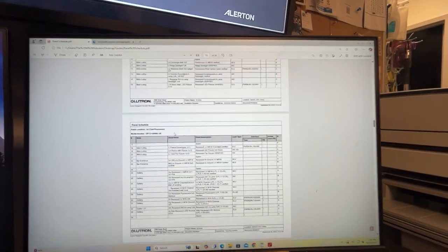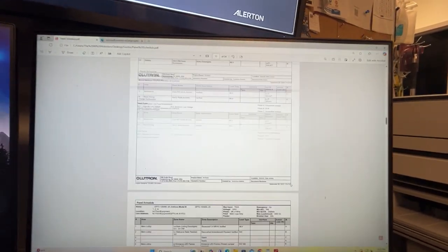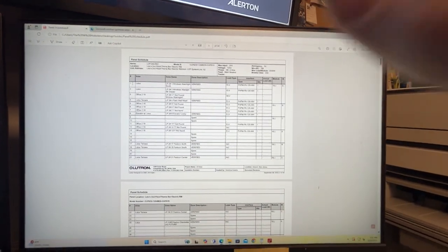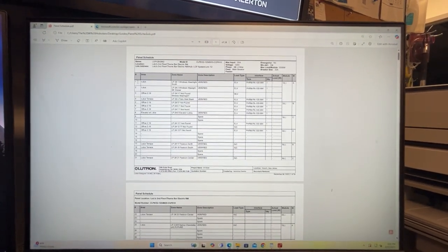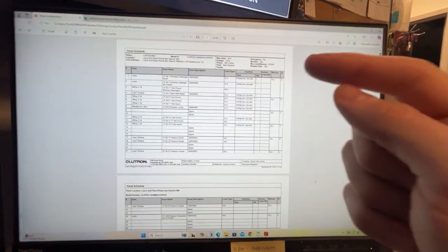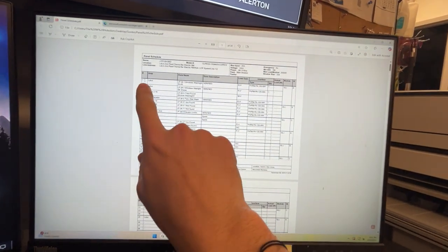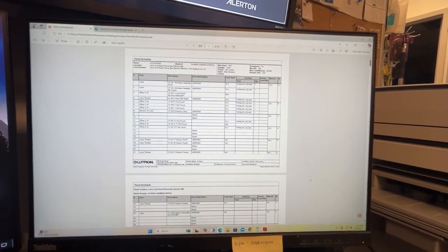And then the last thing is they gave us this really nice up-to-date panel schedule, although I don't really like it because the problem is they updated it. On the breaker panels, the dimming rack panels in the electrical rooms, there's big black dimming panels, right? Each individual breaker, on the breaker itself, there's a number, like a tag on each one, and that pertains to this column. But what they failed to do was there's an original set right here in the shop, dimmer rack schedules.